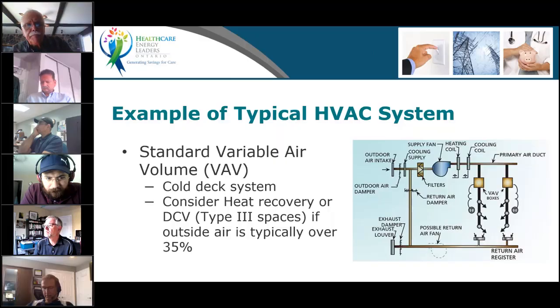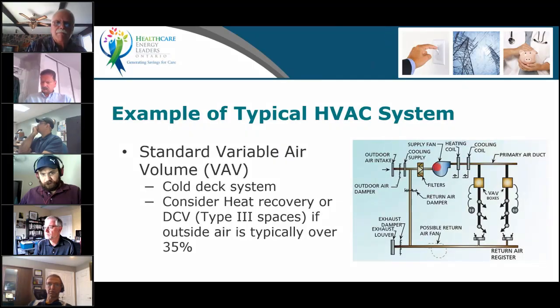I've got an example here of a typical HVAC system that would very often serve what I call the type 3 spaces, the administrative areas. You may have it in other spaces also, but it's very common in those types of spaces. It's a VAV system where you have what I call the cold deck. So you've got your supply fan, I'm going to go here with my drawing tool, and you've got your supply deck. We call that a cold deck because this system is not a heating system.